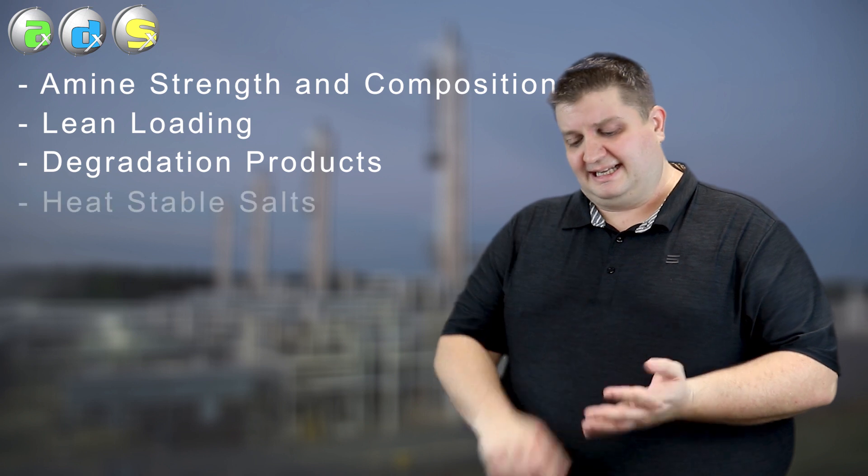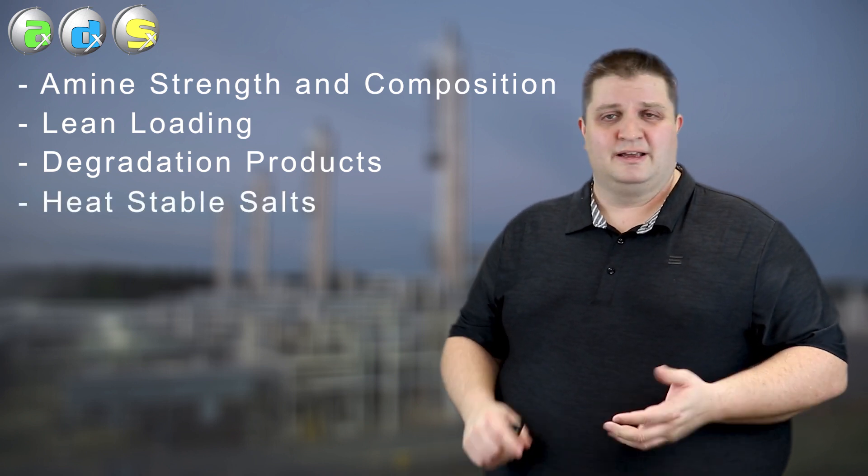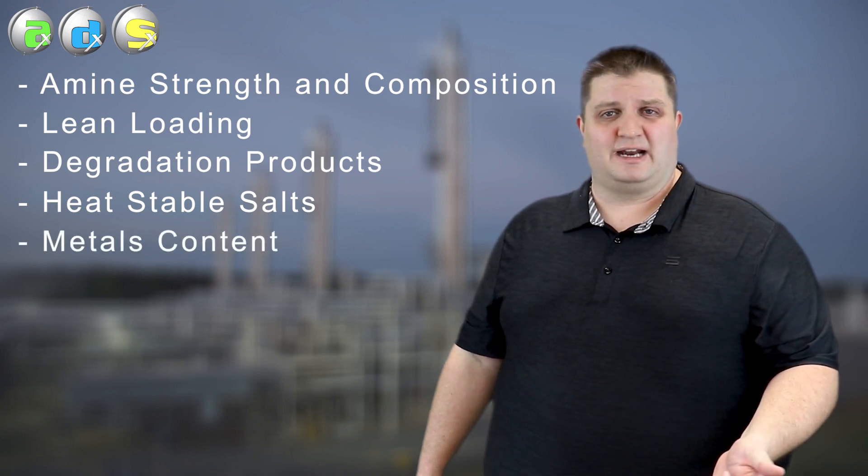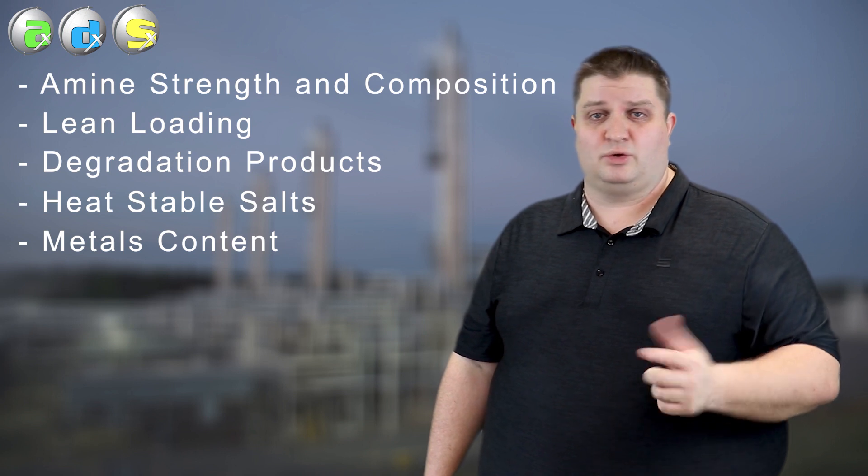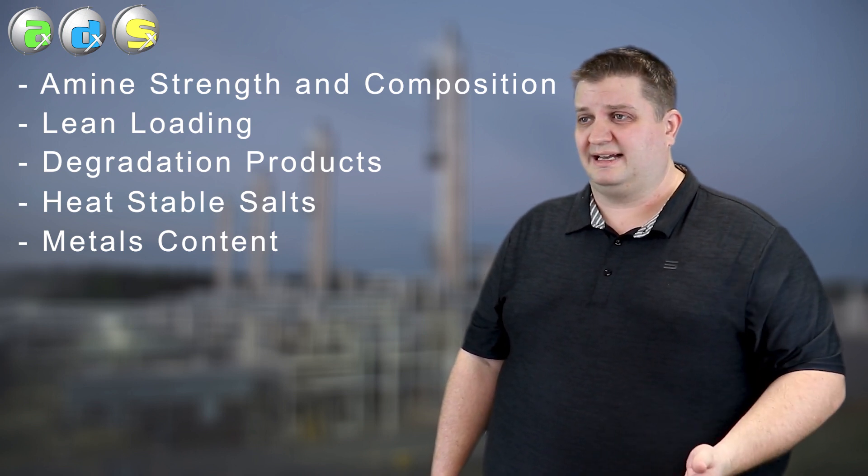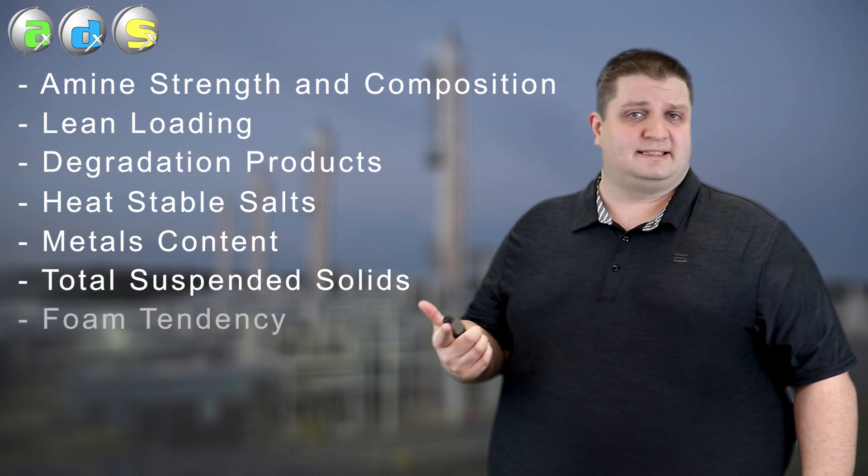Beyond that you're going to get heat stable salts. Not just the overall but each individual type and how much of them there are. You're going to get your metals. Do you have a lot of iron? Do you have a lot of chrome? These are very important to tell you if you have carbon steel or stainless steel corrosion going on in the plant. You're also going to get total suspended solids and some foam tendency of the overall amine.